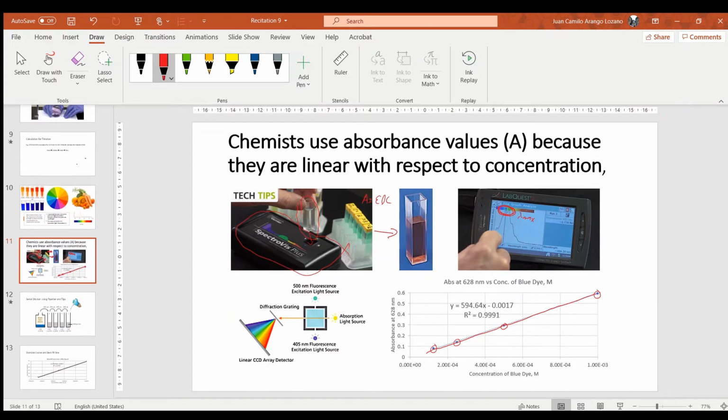With those values, starting from a diluted standard solution, you will be able to have these different points, and once you plot them, because these are just diluted solutions of the same compound, you will be able to make this linear relationship, which is always called the calibration curve. And that calibration curve is going to let you determine the concentration of your unknown.